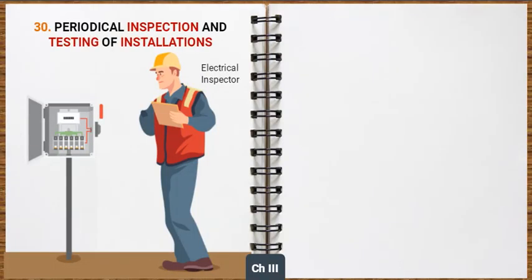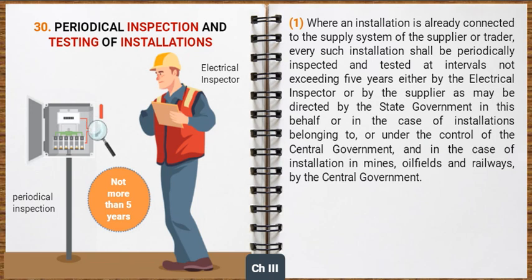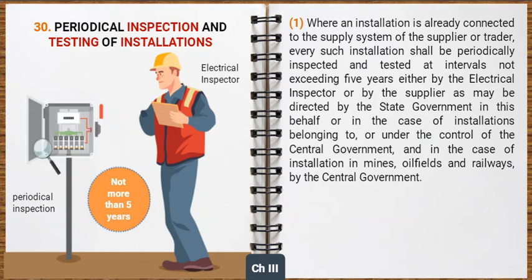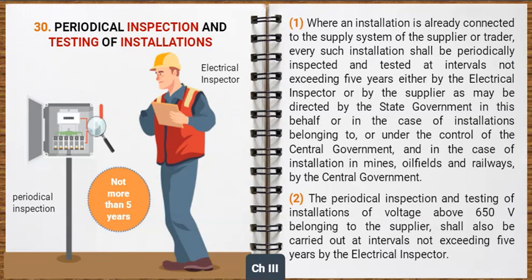Now let's learn the general safety requirements for periodical inspection and testing of installations. Where an installation is already connected to the supply system of the supplier or trader, every such installation shall be periodically inspected and tested at intervals not exceeding 5 years, either by the electrical inspector or by the supplier as may be directed by the state government. In the case of installations belonging to or under the control of the central government, and in the case of installations in mines, oil fields and railways, inspection shall be carried out by the central government. The periodical inspection and testing of installations of voltage above 650 volts belonging to the supplier shall also be carried out at intervals not exceeding 5 years by the electrical inspector.